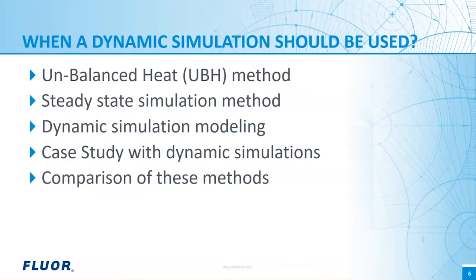First, I will give a brief introduction of three different column relief analyzing methods: the unbalanced heat method, steady-state simulation, and dynamic simulation method. Then I will show the results of these methods by case studies of two different distillation systems — the sour water stripper and the ethanol column — with global upset scenarios such as total power failure and partial power failure. In the end, I will discuss the pros and cons of these methods and shed light on where and when to apply them.